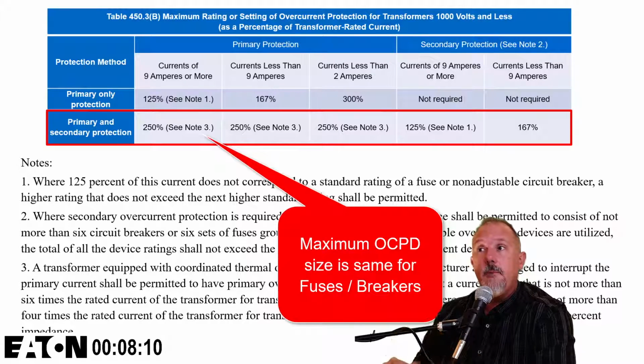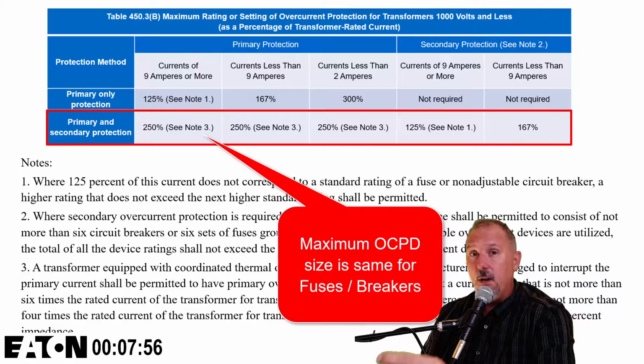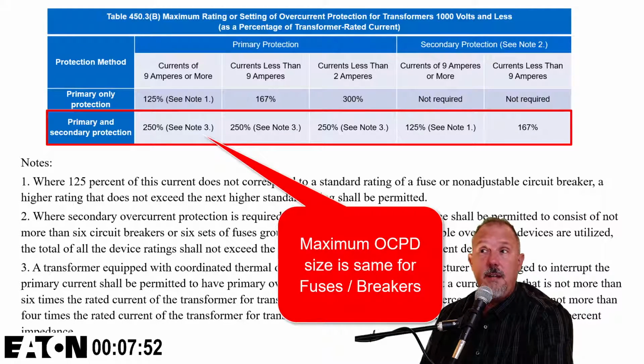In any case, this table is going to give me my multiplying factors, and I know that I'm going to be putting primary and secondary protection. Again, to use that first row at 100, even if I use 125% for my primary overcurrent protected device, it is very rare that you will not have a secondary overcurrent protected device on the secondary of that transformer when you have a panel board downstream.